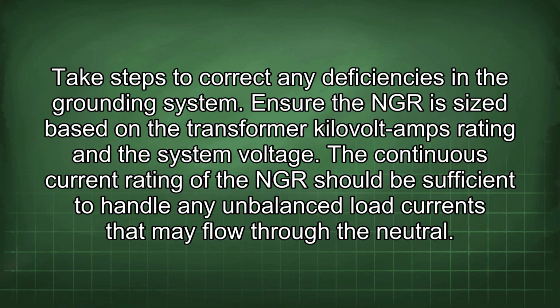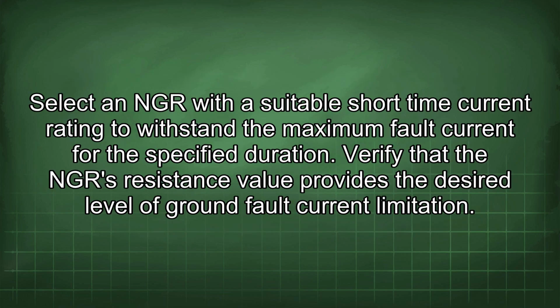Ensure the NGR is sized based on the transformer kilovolt-amps rating and the system voltage. The continuous current rating of the NGR should be sufficient to handle any unbalanced load currents that may flow through the neutral. Select an NGR with a suitable short-time current rating to withstand the maximum fault current for the specified duration. Verify that the NGR resistance value provides the desired level of ground fault current limitation.